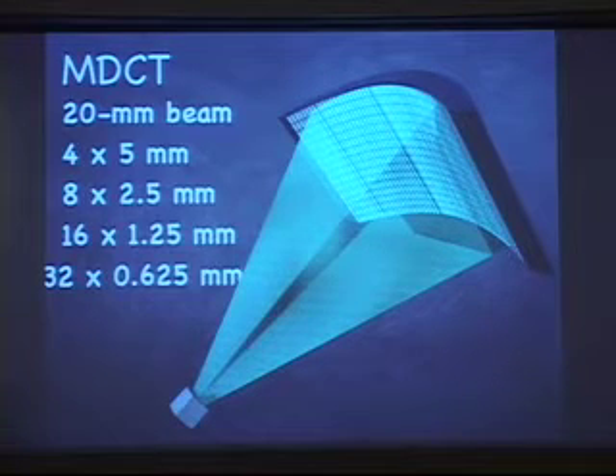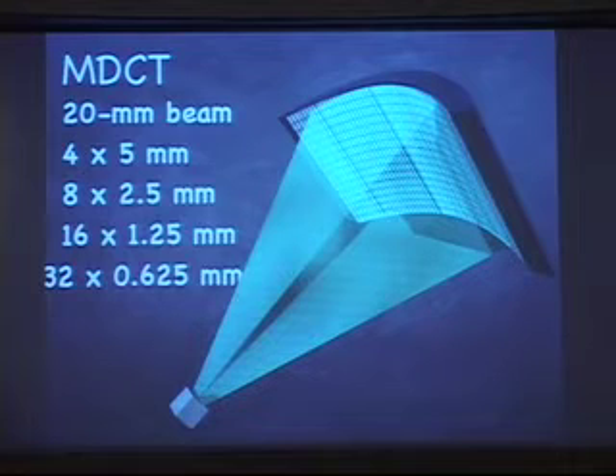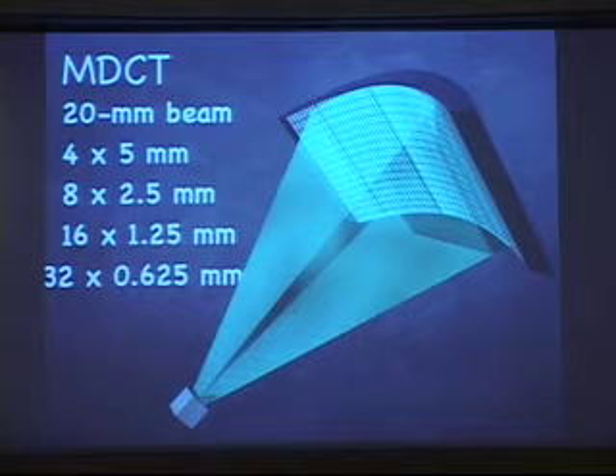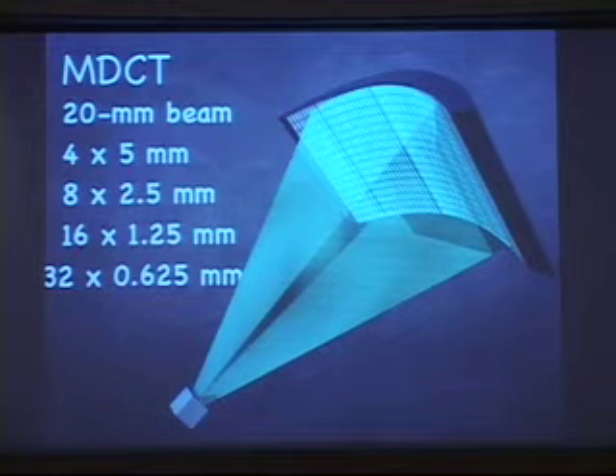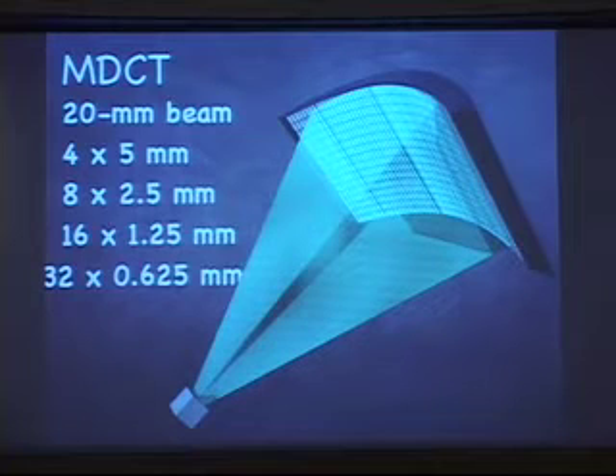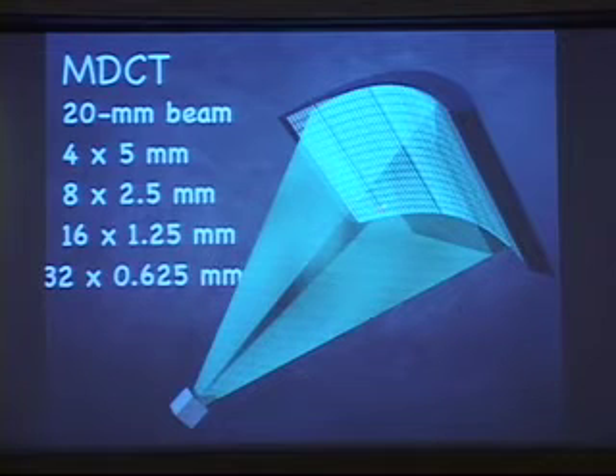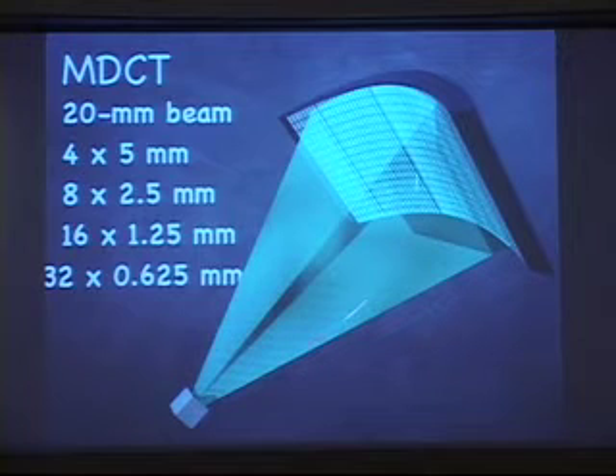to 0.625, and the current state of the art in CT is that the fundamental detector width is anywhere from 0.5 to 0.6 millimeters. And CT scanners are now available with up to 320 rows, although the 320-row scanner has a very limited penetrance and is still, I would say, relatively investigational. But 64-row is certainly a very common CT technology that's available broadly. The way 64-row is implemented is we have a 40 millimeter detector and a 40 millimeter beam and 64 by 0.625 millimeters.